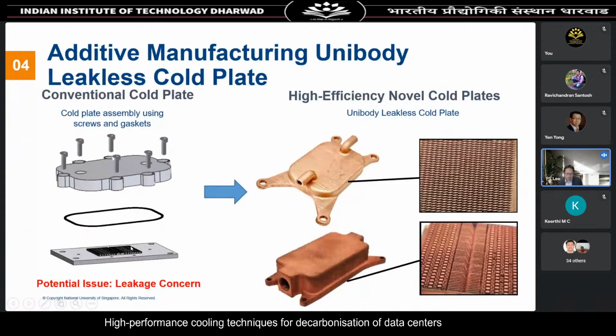On the left is a conventional cold plate design, where the fins are fabricated on the base plate separately from the top cover. In order to seal the cold plate, you need to use mechanical sealing with bolts, nuts and O-ring gaskets, or a brazing process. This incurs additional cost and time, and is subject to leakage, because most of the time the joints are not perfect.